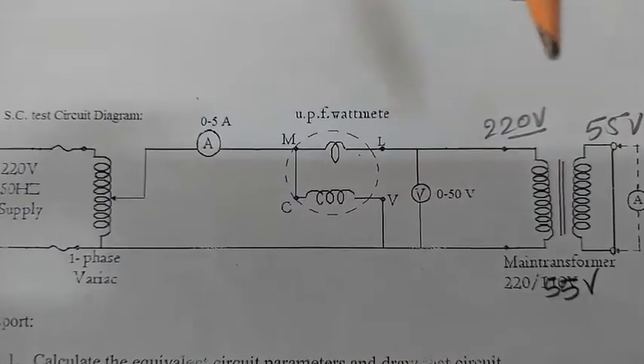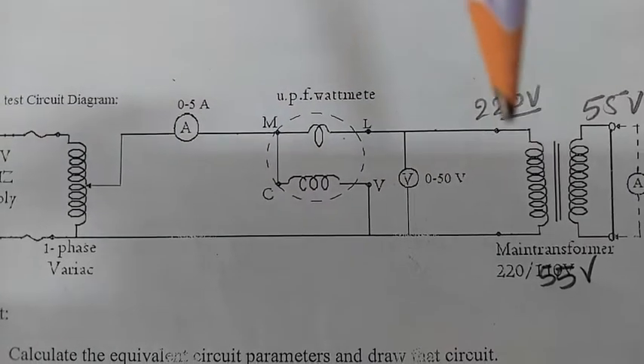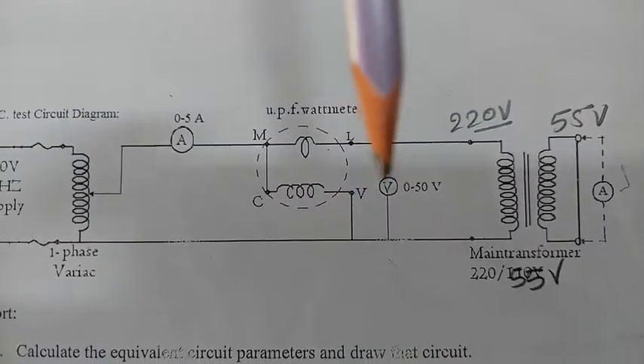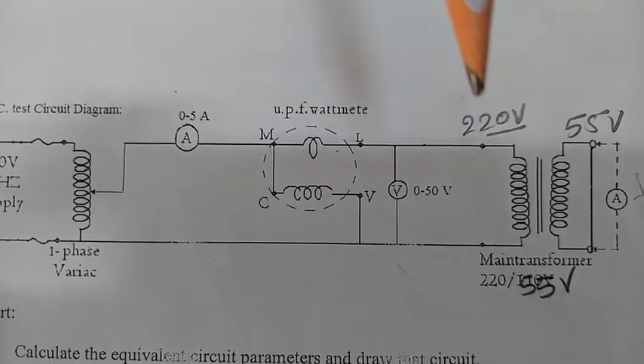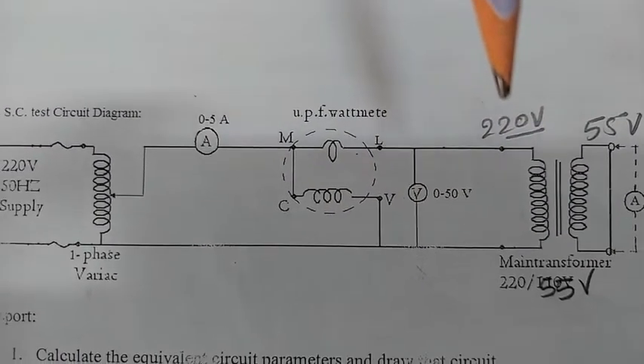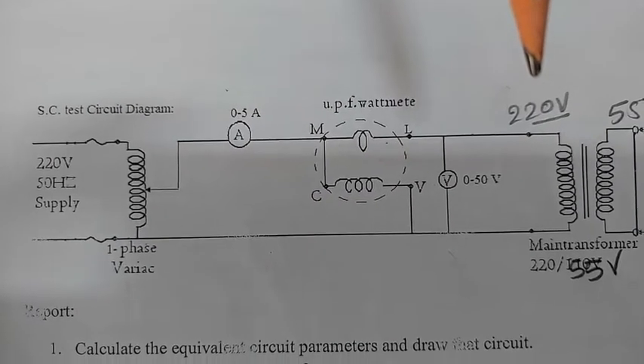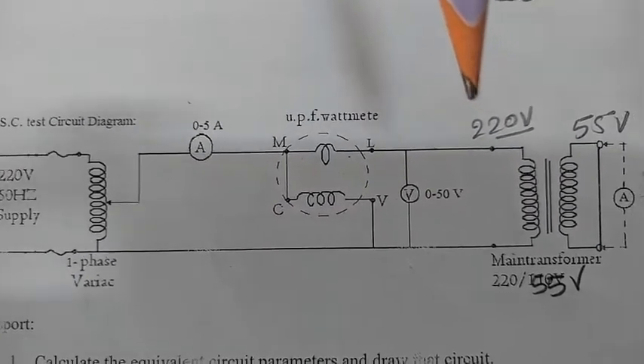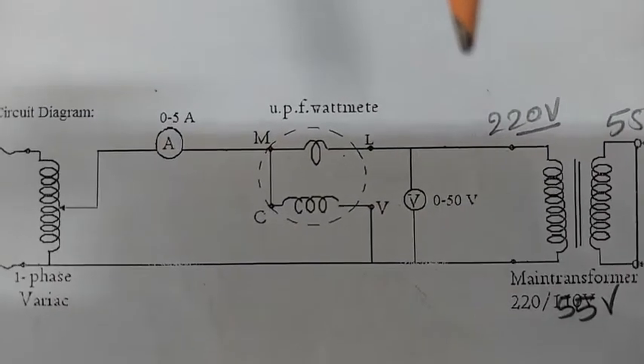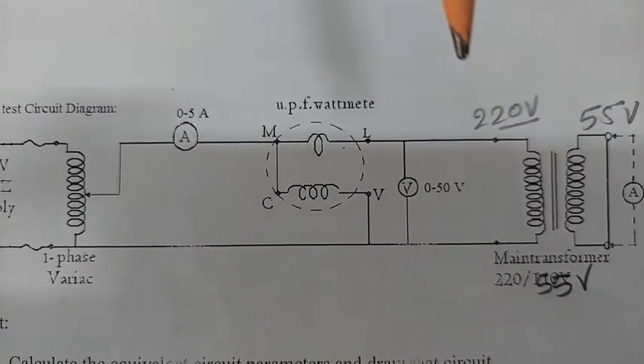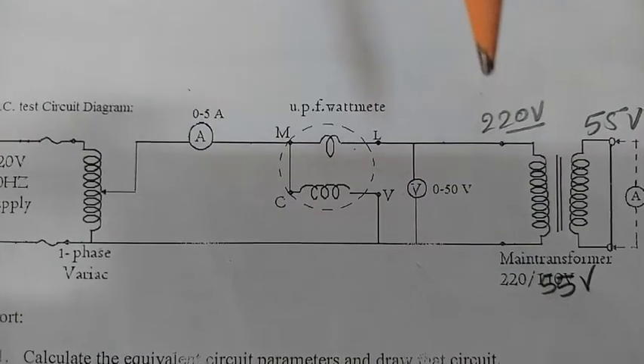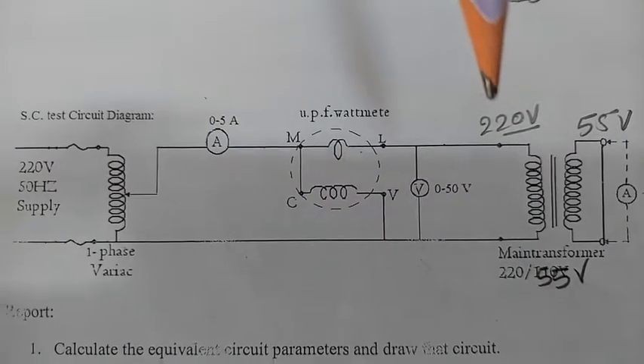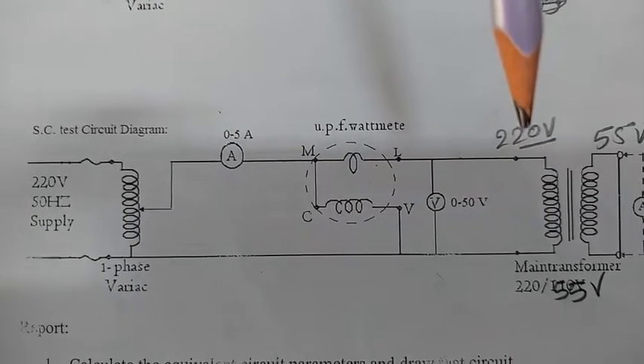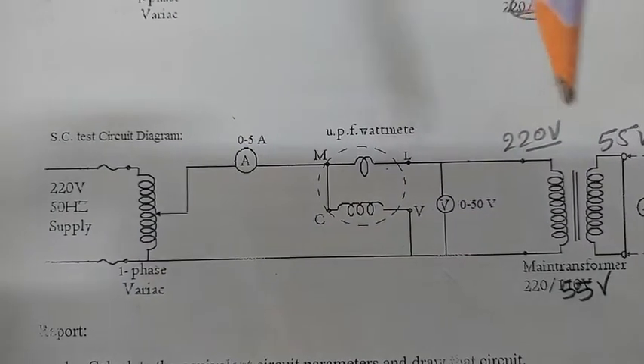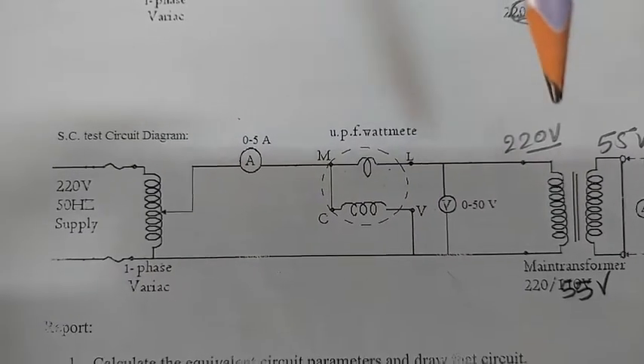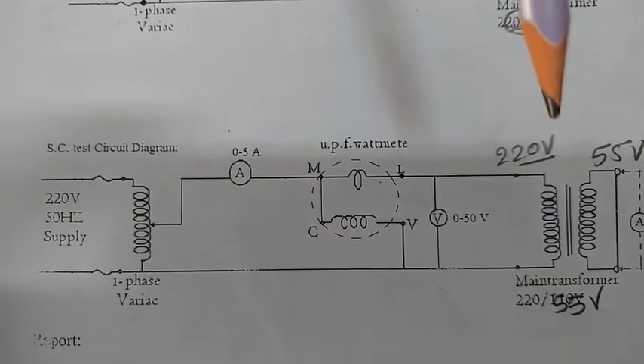And after that, we will see that there is one voltmeter which is connected in parallel, as voltmeters are always connected in parallel. That voltmeter will be measuring the primary voltage or input voltage, that is how much voltage we are giving. So we will be changing the voltage on the variac side. We will be reading that voltage continuously on the voltmeter shown here. A 0 to 50 volt range is very suitable, but any voltmeter can be connected. But here the voltage required for this experiment will be 5 to 15% of the full load voltage, that is 5 to 15% of the 220 volt side, where 220 volt is the rated voltage.